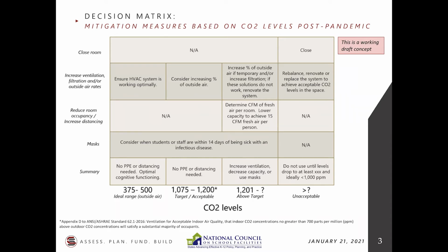And the reason is that occupancy is variable. You might have economizers kicking in that typically would not on a routine basis. There may be some sort of caveat, something that you have to take into account for that given day that may be influencing and drawing those CO2 levels lower. So if you're above a certain value, hey, I've got to fix that. If you're below it, you need to look further to really feel like you're doing the right job.